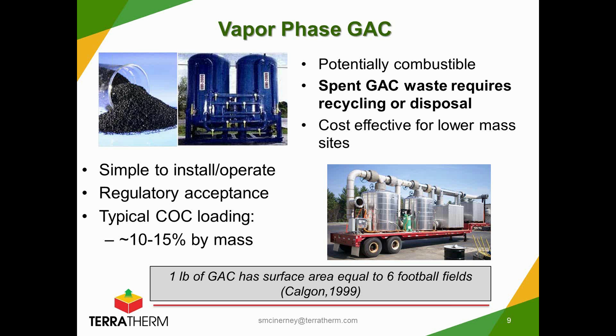The range of contaminants may average about 10 to 15% by mass contaminant absorbed to the carbon media. And of course, that can be much higher for certain contaminants and much lower for items like, say, vinyl chloride. Much lighter, lower molecular weight, highly volatile compounds can tend to be significantly lower than that 10 to 15% range, but that's sort of a rule of thumb.